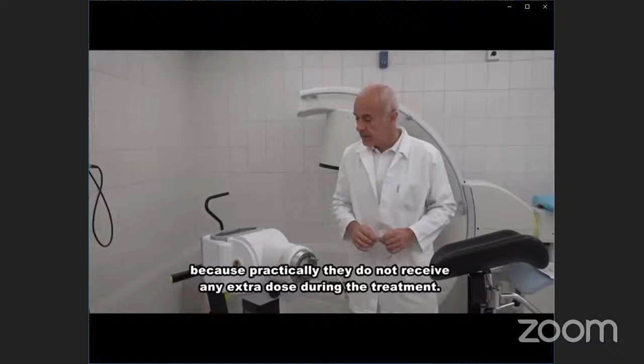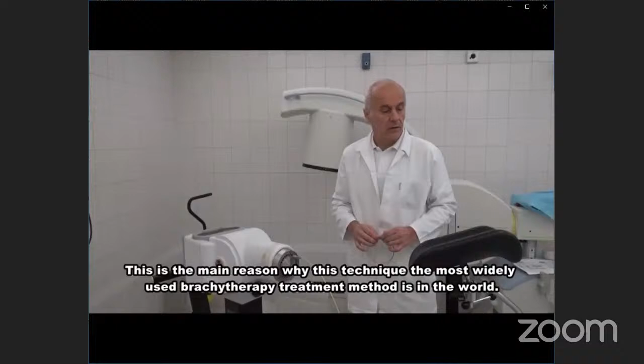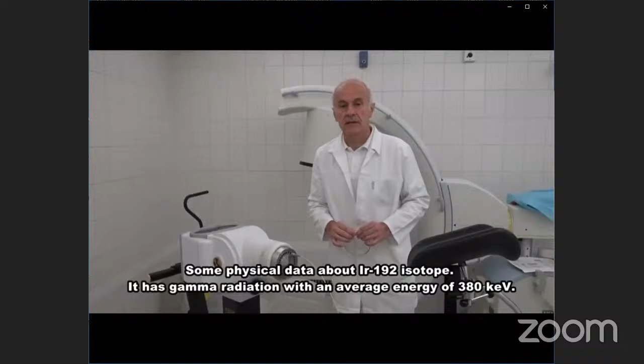This afterloading technique is very safe regarding the radiation protection of the staff because practically they don't receive any extra dose during the treatment. This is the main reason why this technique is the most widely used brachytherapy treatment method in the world. Some physical data about the iridium-192 isotope. It has gamma irradiation with average energy of 380 kiloelectron volts. As you know, gamma radiation is electromagnetic radiation, and the half-life of iridium-192 is 74 days. During this time period, the original activity will be half, and the treatment time will be double. As the activity decreases, the treatment time will increase continuously.